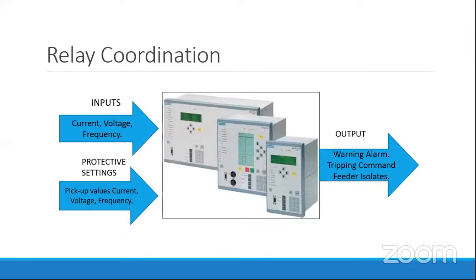It should raise an alarm as well as a tripping command, so that we get to know that the system has gone faulty or an abnormal condition has been raised in the network. We should take the necessary actions and give tripping commands to the breakers associated with this relay, and it should isolate the faulty feeders, and we can save the healthy system.